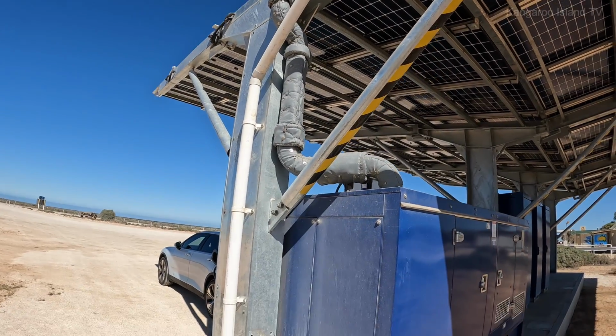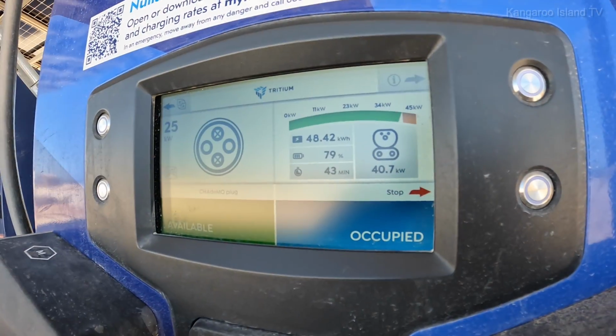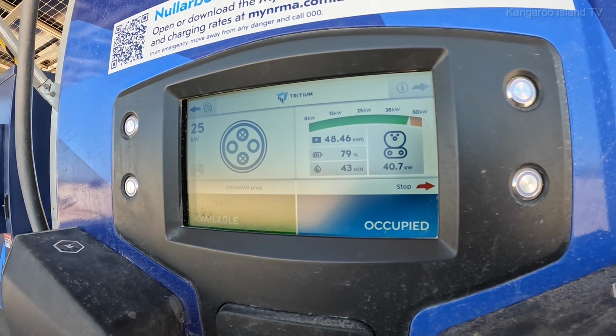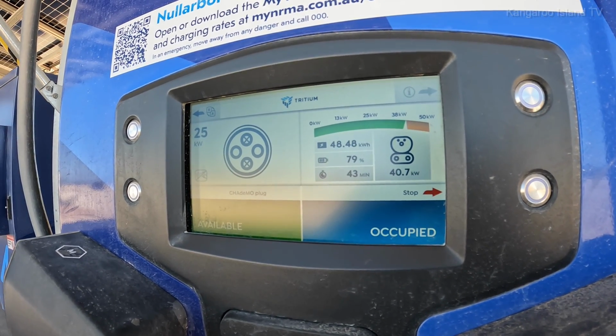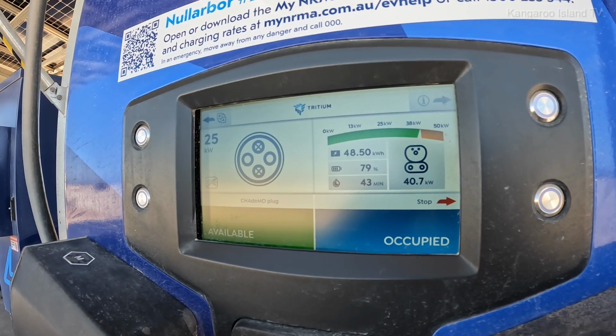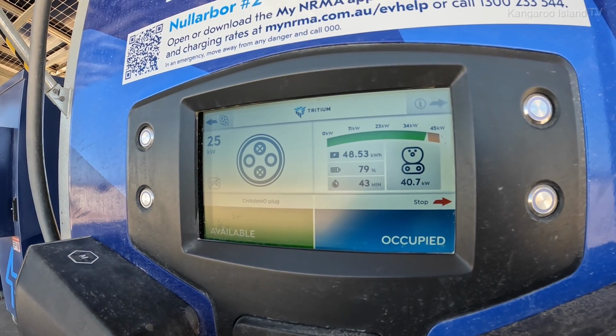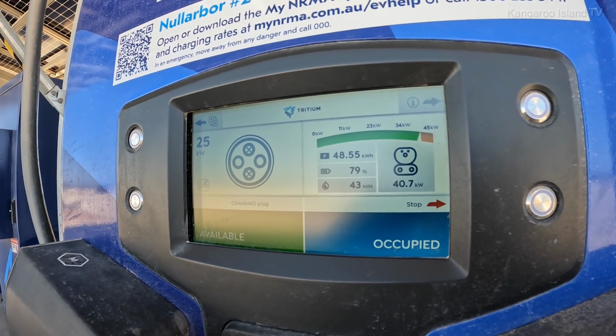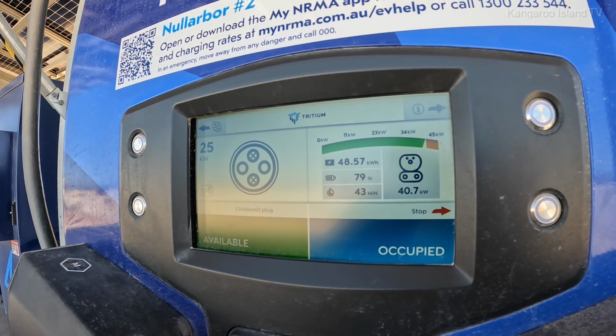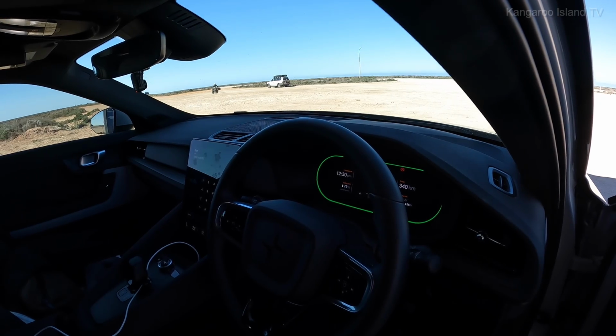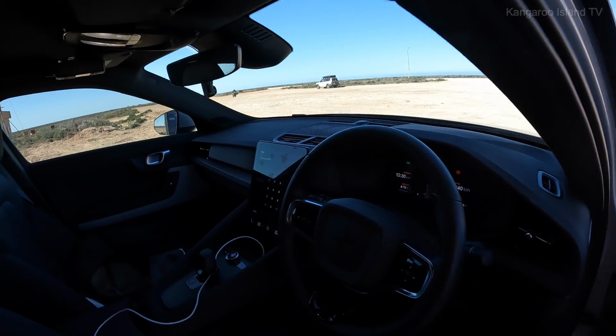So we're down to 40 kilowatts, and it's been going for 43 minutes, we've taken 48 kilowatt hours. So it's only got another 15 minutes to go, so we'll be exactly an hour to do that. 80%. We'll go the full 90.